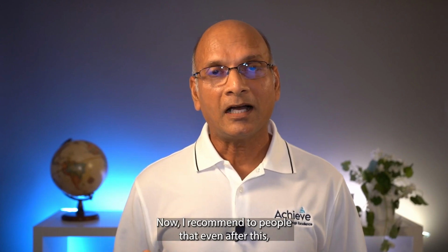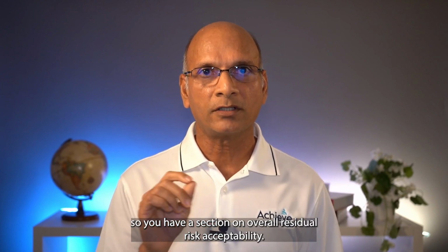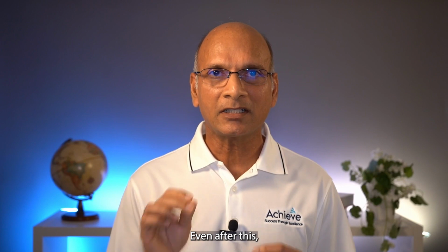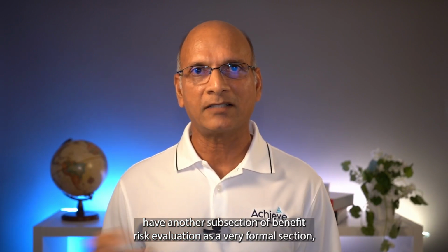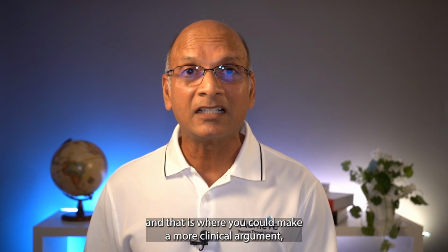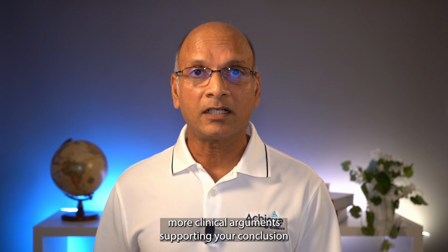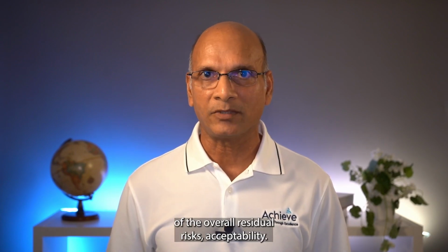Now, I recommend to people that even after this, so you have a section on overall residual risk acceptability, even after this, have another subsection of benefit risk evaluation as a very formal section. And that is where you could make a more clinical argument supporting your conclusion of the overall residual risk acceptability.